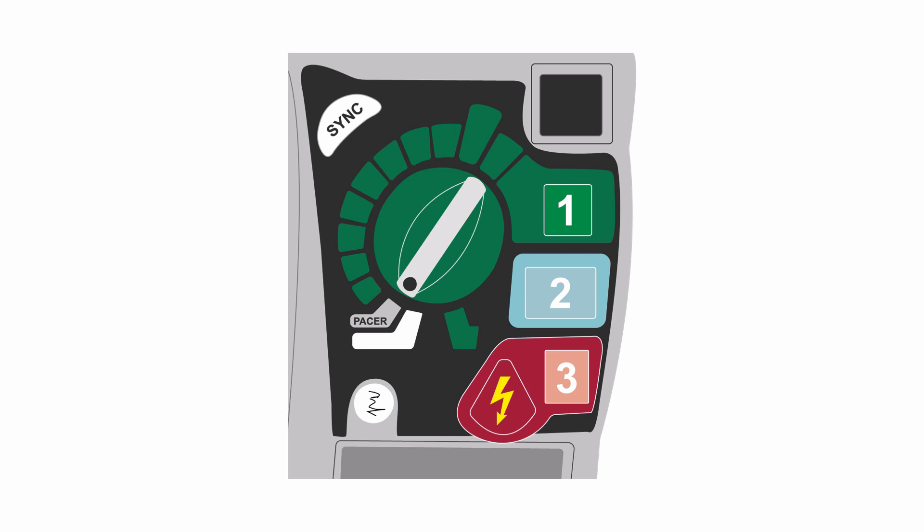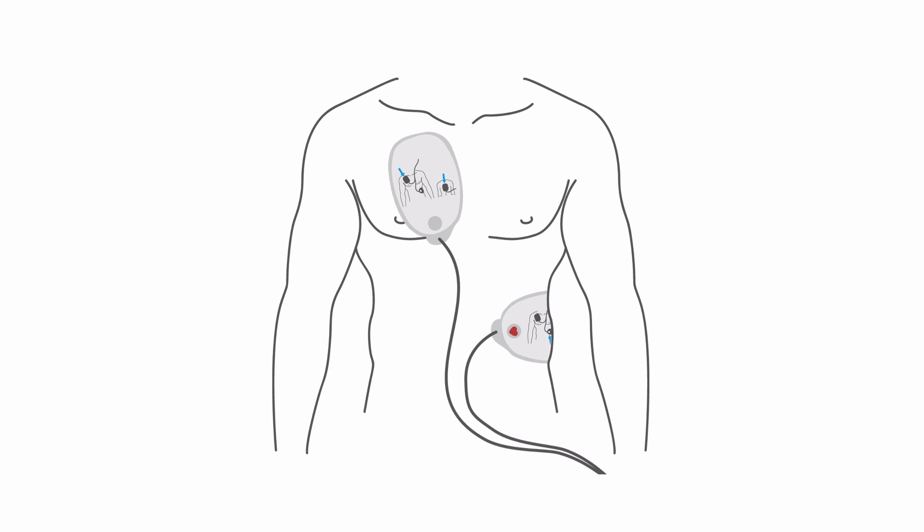Most defibrillator machines can be converted to a transcutaneous pacer by turning on the pacer feature. Pacer pads are placed in the same way as a defibrillator, but because the pads cannot both sense and pace at the same time, you have to connect the monitor leads to the machine.